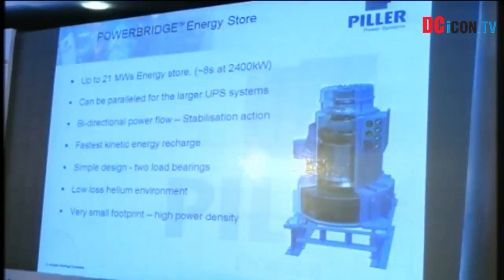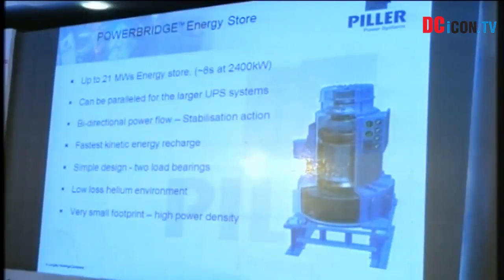It can absorb as well as discharge, so bidirectional flow is possible. Fastest kinetic energy recharge. In batteries, you could buy a 30-minute battery, but then to get it recharged, it takes maybe 12, 13, 14 hours, sometimes even a day, to be ready for your next power outage. Whereas the recharging time here is less than minutes, 2 minutes, 3 minutes. So we are talking about minutes here and not about half a day or maybe even a day.